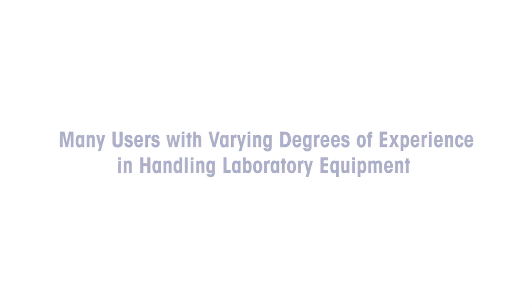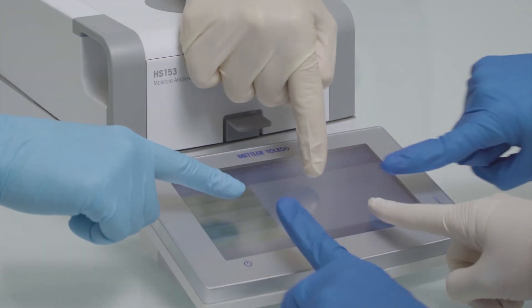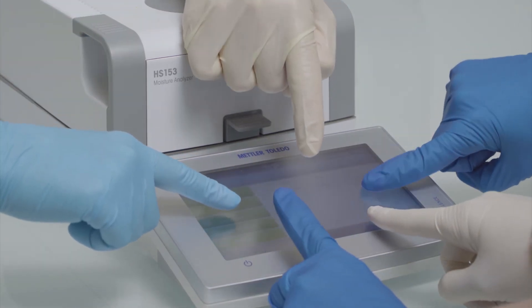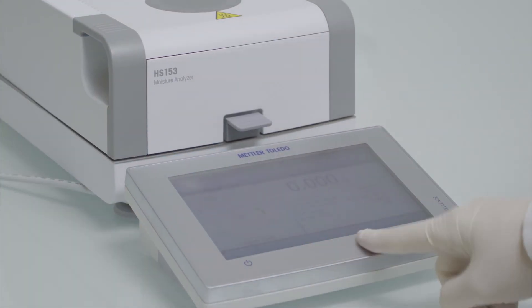In most cases, the reference method for moisture content determination is the drying oven. With this method, a measurement takes several hours, compared to only a few minutes with the moisture analyzer. With the help of the method wizard function and the method collection for pharma excipients, you can validate the moisture analyzer as an alternative method for moisture content determination.